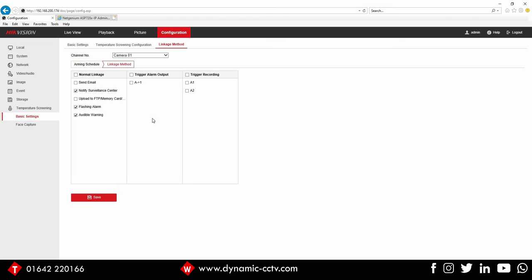So under linkage method, we've got your normal linkage here. Now the audible warning tick box here is for the embedded message within the camera, so we're going to untick that. We're going to tick the trigger alarm output, and that alarm output is in turn going to trigger the alarm input on our NetGenium speaker.